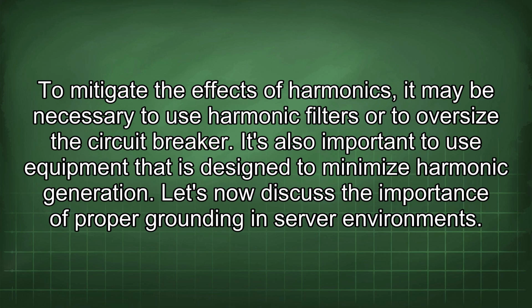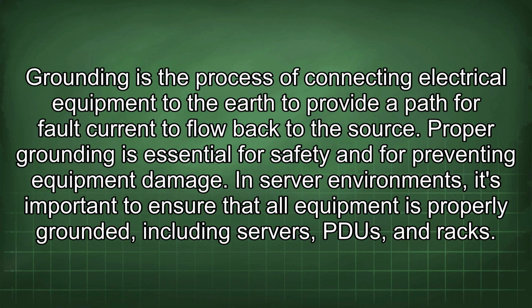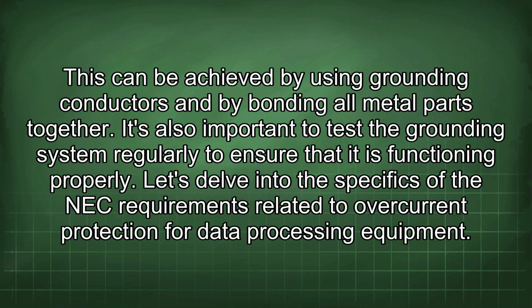Let's now discuss the importance of proper grounding in server environments. Grounding is the process of connecting electrical equipment to the earth to provide a path for fault current to flow back to the source. Proper grounding is essential for safety and for preventing equipment damage. In server environments, it's important to ensure that all equipment is properly grounded, including servers, PDUs, and racks. This can be achieved by using grounding conductors and by bonding all metal parts together. It's also important to test the grounding system regularly to ensure that it is functioning properly.